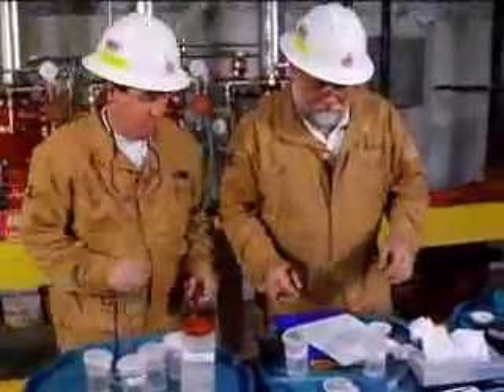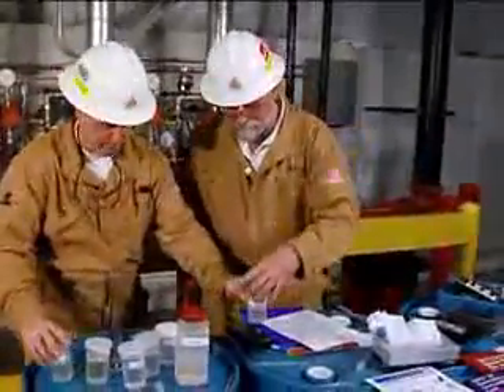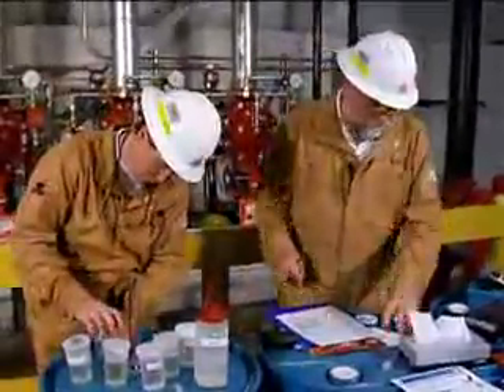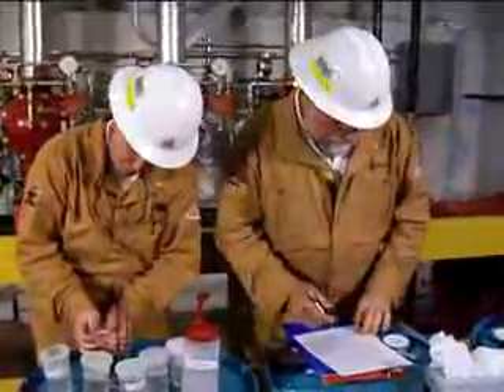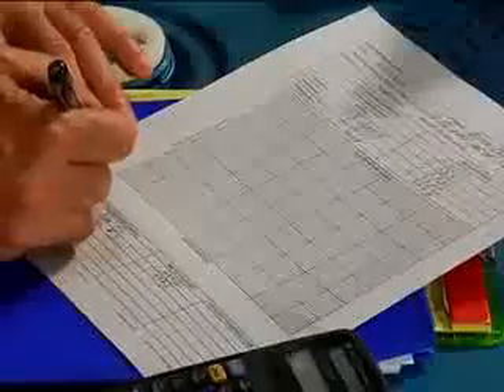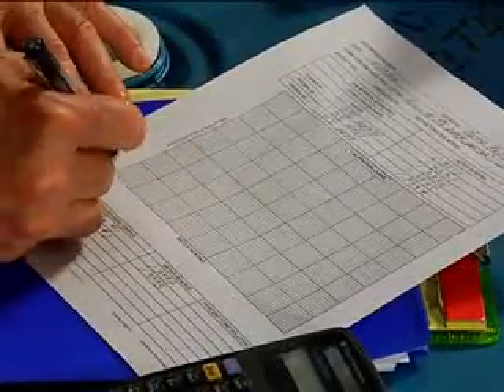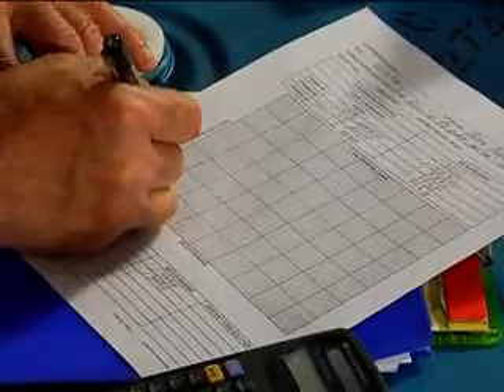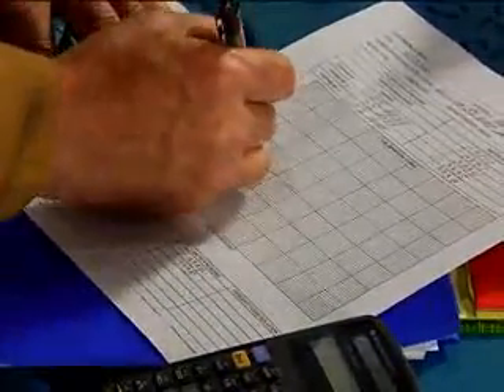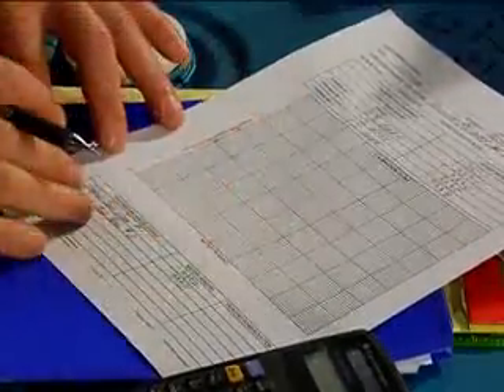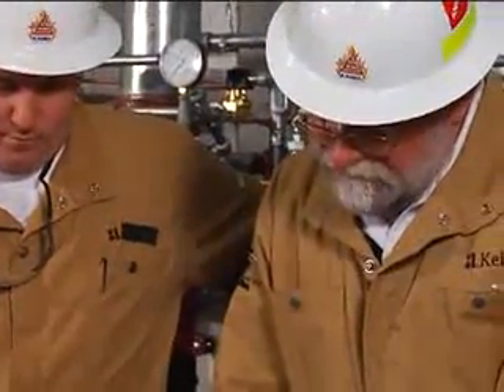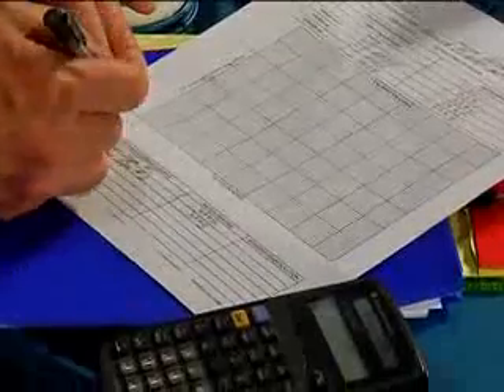Commission testing the Ansul bladder tank. Proportioning system, known concentration graph. So we need to determine what those numbers mean, what concentration those samples are. And so on the form, we have a grid that we can plot out percent concentration. On the Y-axis, we're going to put concentration percentage: 0%, 1%, 2%, 3%, 4%, 5%. On the X-axis, we're going to put refractive index readings, again creating a linear scale.